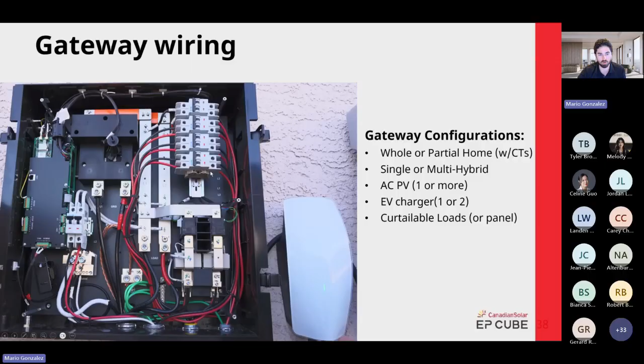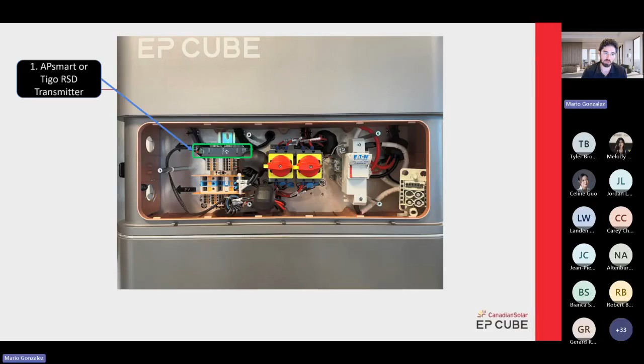Now we're going to talk about the hybrid inverter and the components inside it. So this is what you will see inside the hybrid inverter. This is the AP Smart or Tigo RSD transmitter. Basically, you need to put RSD devices, only RSD, don't use optimizers or anything like that. Just use rapid shutdown devices, either Tigo or AP Smart. Whenever you purchase the inverter from the manufacturer, make sure you have the one with the right transmitter because it comes pre-wired from factory. If you get the wrong one, you're going to have to source your own transmitter and wire it yourself.